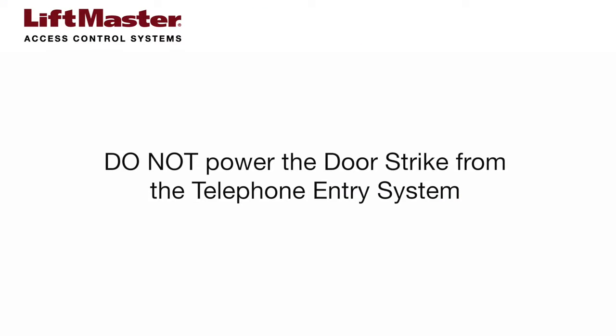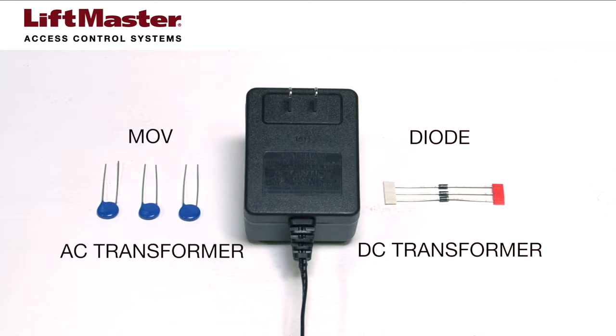Do not use the telephone entry system to power the door strike, no matter which door strike you choose. The door strike must have a separate power transformer. You will need to connect either an MOV or a diode depending on whether the power transformer is AC or DC.